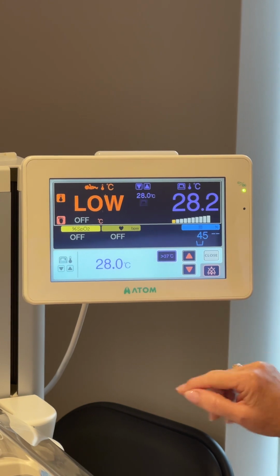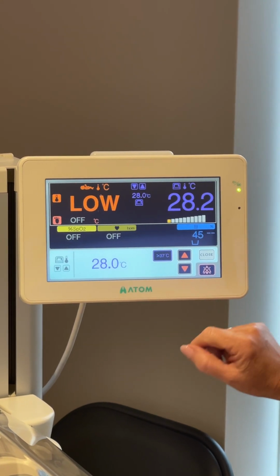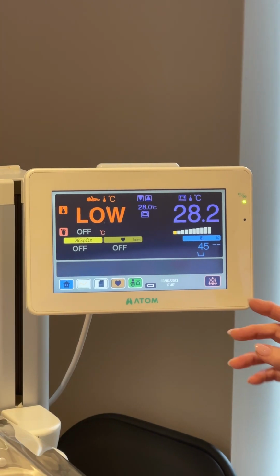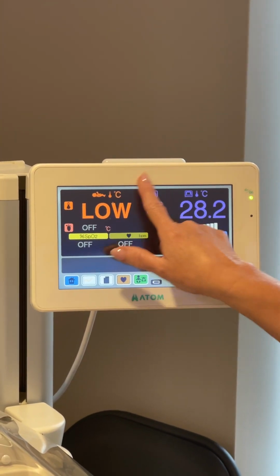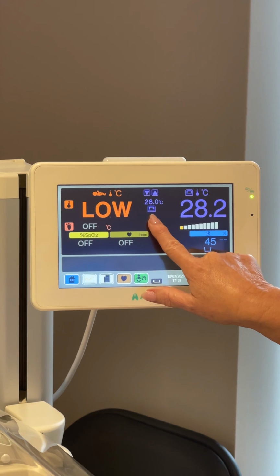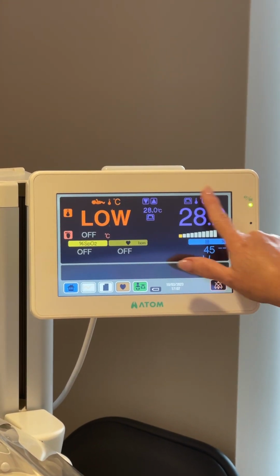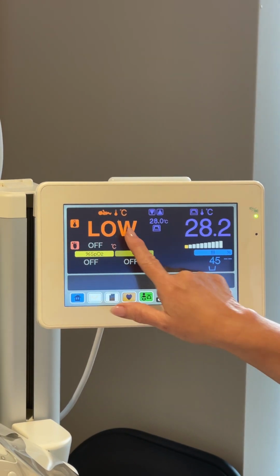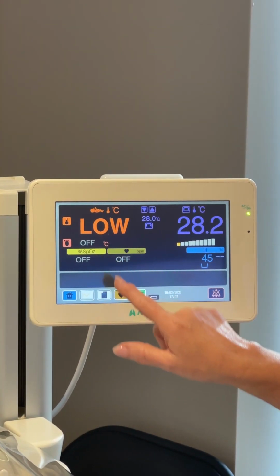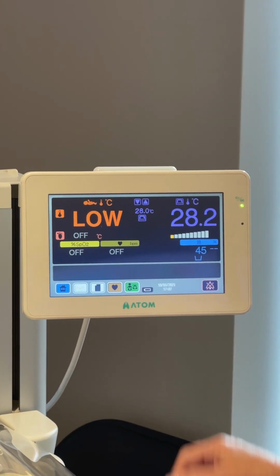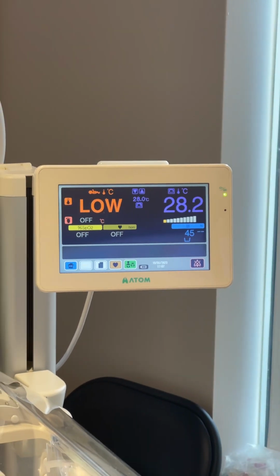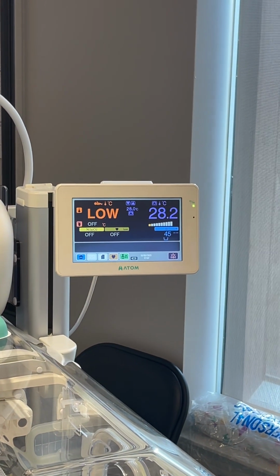So the active change keys, you can put your set point in and push close, or in 8 seconds it'll close itself behind me and make my changes. When I'm looking at the screen, the mode and set point is here, the actual air temperature is here, and your baby's temperature would be here in orange. Everything baby-associated will be orange. The temp probe's just laying in there right now, so it just reads low, but we do want skin temp for your servo mode, which is the abdomen.